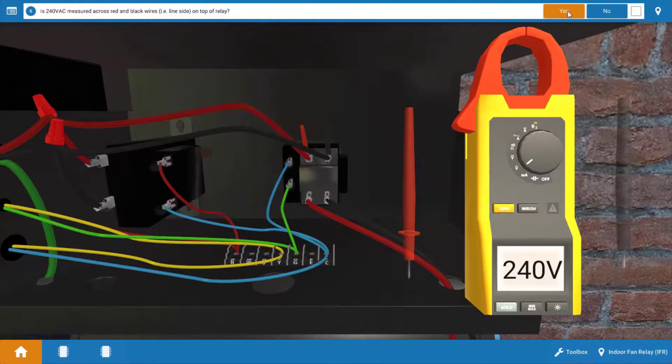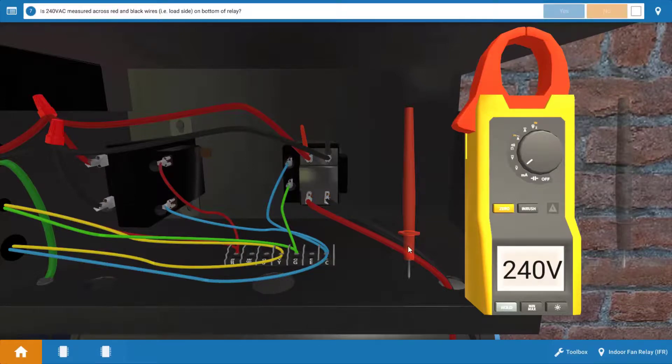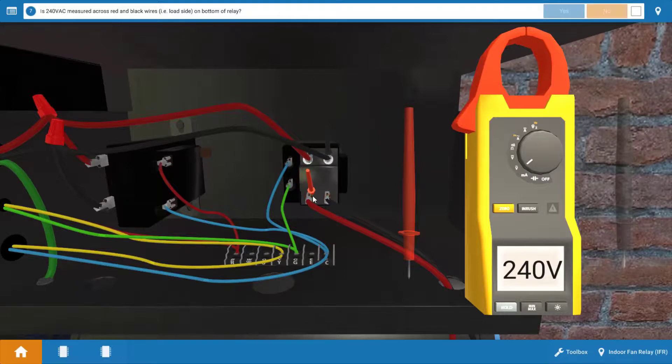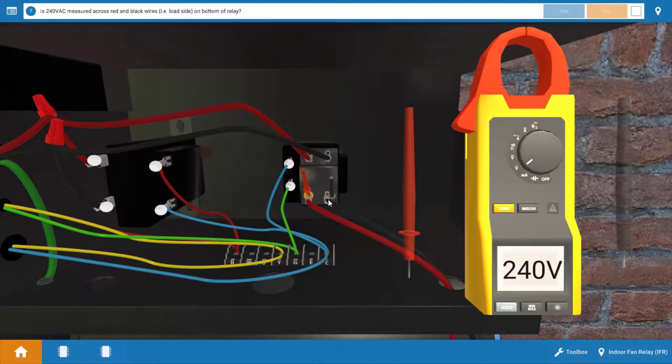Now we need to check and see if we have load side voltage. In other words, is the relay actually pulling in and allowing 240 to the motor? Well, again, we'll check the load side voltage by dropping the meter leads on the glowing orange hotspots at the load side of the relay. And we can see here we have 240 volts.